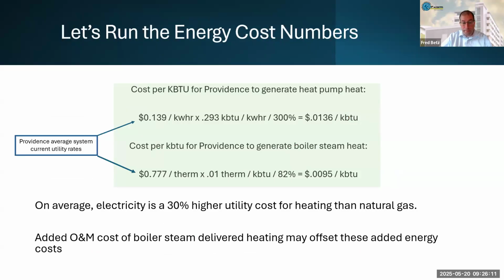So the other challenge here is the cost of electricity versus the cost of gas. And Jeff was nice enough to put these together for their system, so we knew what we were getting into. But it's about a 30% premium per kBTU of heat provided using electricity versus natural gas, just as a straight conversion. And so there's a bit of an uphill climb here. So we need to do this as efficiently as possible. You do get, as you saw on the previous slide, the COP benefits this somewhat. So you need to have fewer BTUs, but we do need to account for this in order to make this whole thing cost effective.